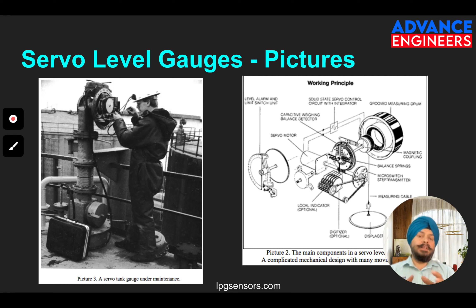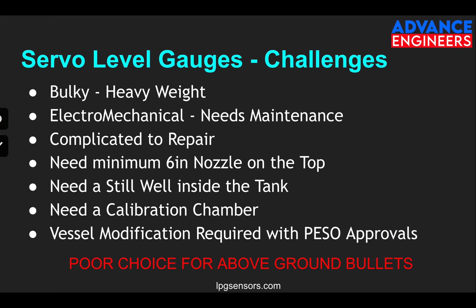But if it's an old, existing vessel where you want to install a servo level gauge, it's always recommended to get a structural analysis done for load calculation, since you'll also need a still well added. The total weight could be more than 1.5 tons, so the vessel must withstand that pressure and weight without damage. So first is the bulky and heavy weight.